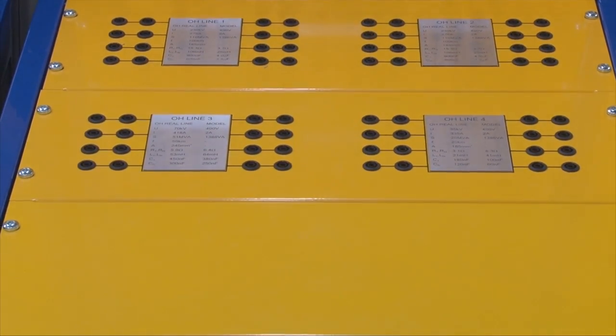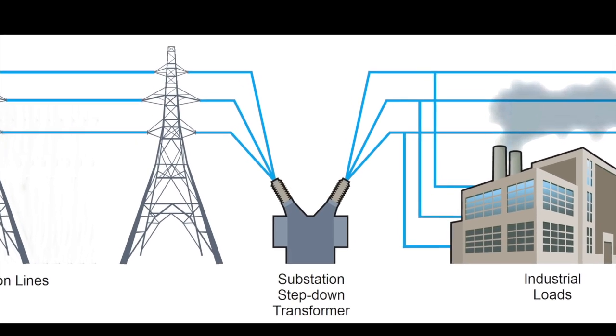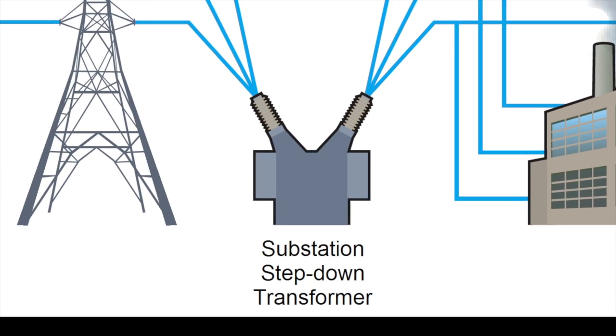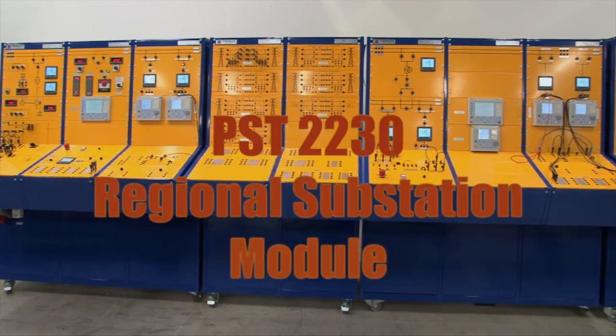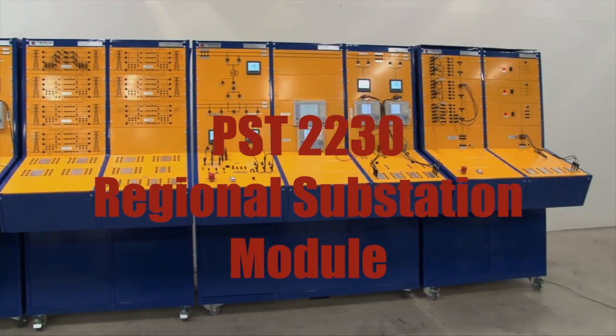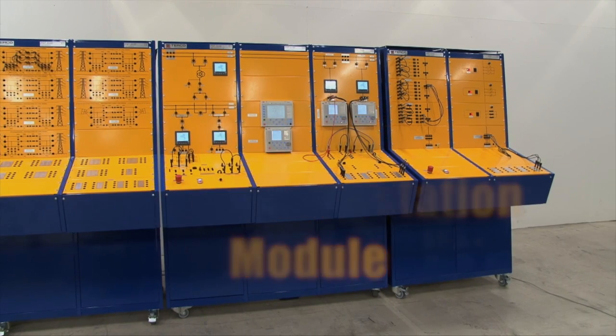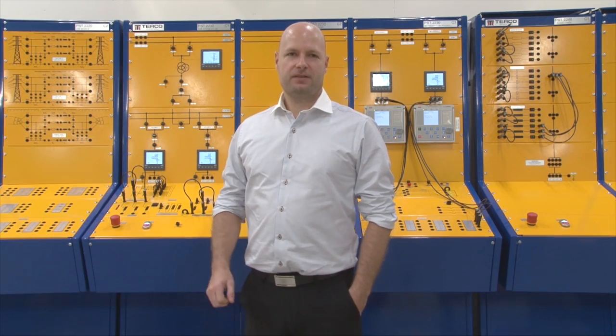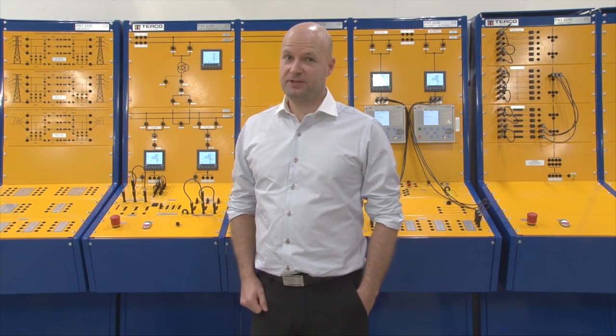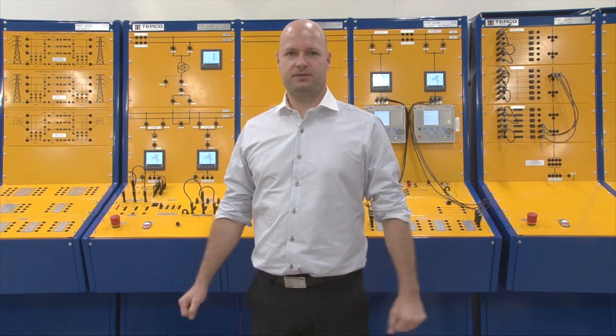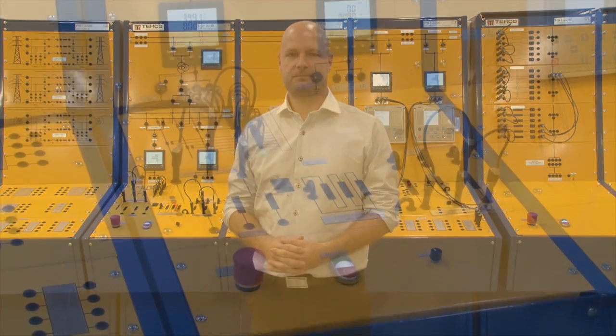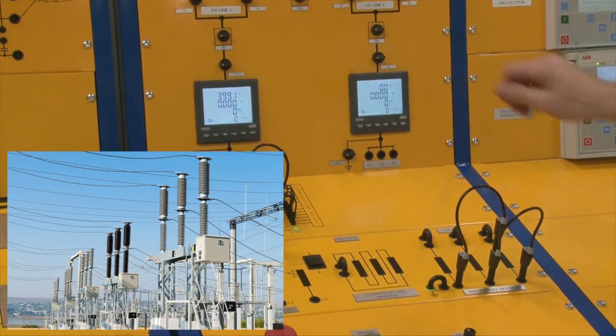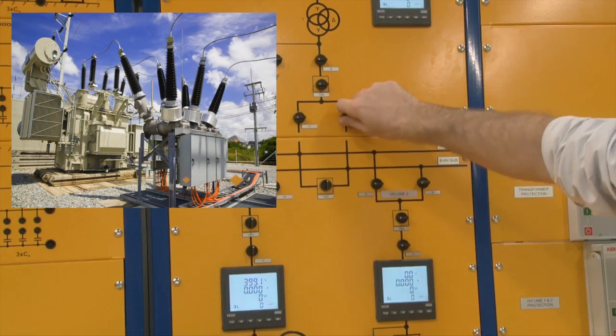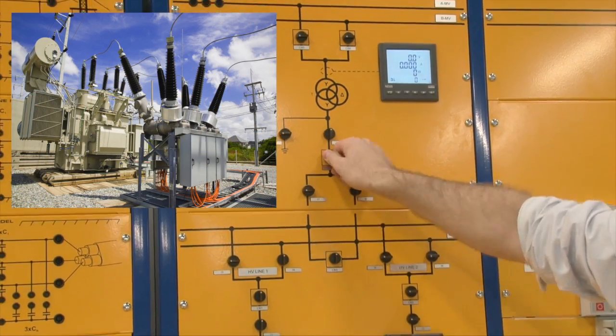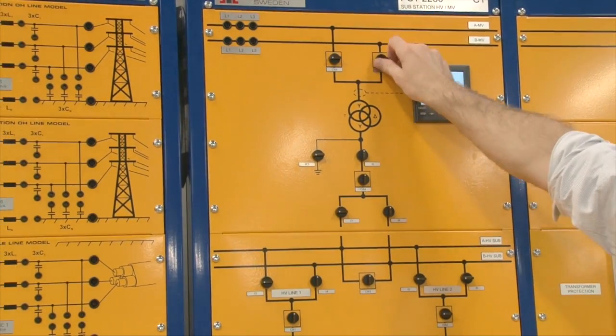As power nears the end consumer, the high voltage must be scaled down to more practical levels. This is one of the main jobs of a substation. The PST 2230 Regional Substation module is the hub of the simulated power network. Here the incoming voltage is received from distant generation stations onto the dual HV bus via the switchgear. This voltage is then transformed down in magnitude and distributed out to distribution lines from the two outgoing feeders.